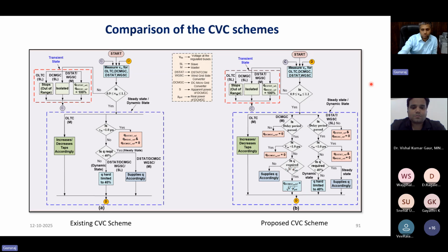Now, this is a conventional OLTC scenario, but in this particular case study, we didn't assume a conventional mechanical OLTC. Rather, we have assumed a solid state transformer where there is no bound on the number of tap changes. Perhaps we have assumed that we don't want to change too frequently. The reason being, if we keep on changing the voltage profile, then that will affect the other sensitive loads as well. So we have kept a bare minimum time duration and a threshold of voltage limits, and ensure that if the voltage change is there for a significant amount of time, then the voltage tap changing is initiated, but the limit of the operation range is 0.9 per unit to 1.1 per unit.